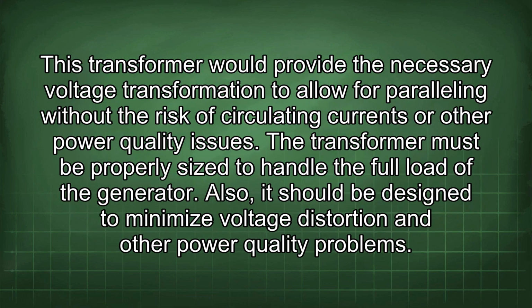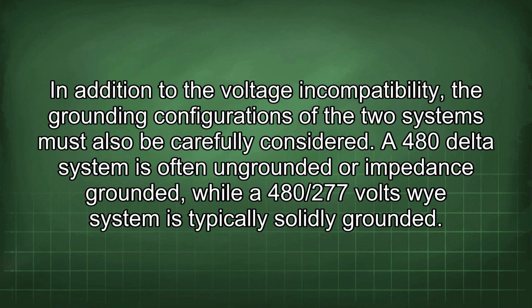This transformer would provide the necessary voltage transformation to allow for paralleling without the risk of circulating currents or other power quality issues. The transformer must be properly sized to handle the full load of the generator. Also, it should be designed to minimize voltage distortion and other power quality problems. In addition to the voltage incompatibility, the grounding configurations of the two systems must also be carefully considered.